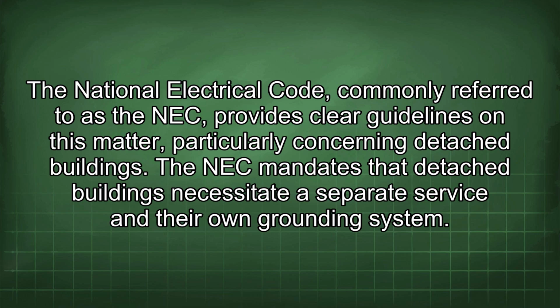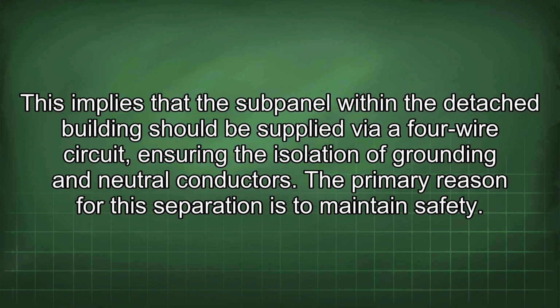The National Electrical Code, commonly referred to as the NEC, provides clear guidelines on this matter, particularly concerning detached buildings. The NEC mandates that detached buildings necessitate a separate service and their own grounding system. This implies that the subpanel within the detached building should be supplied via a 4-wire circuit, ensuring the isolation of grounding and neutral conductors. The primary reason for this separation is to maintain safety.